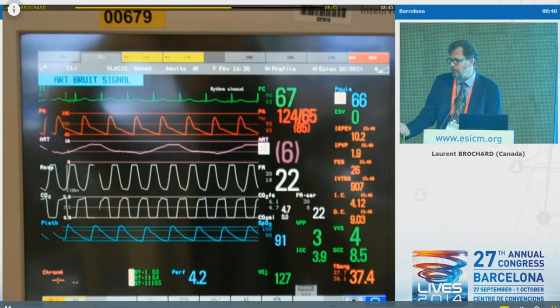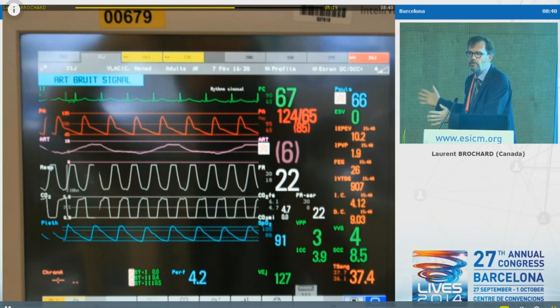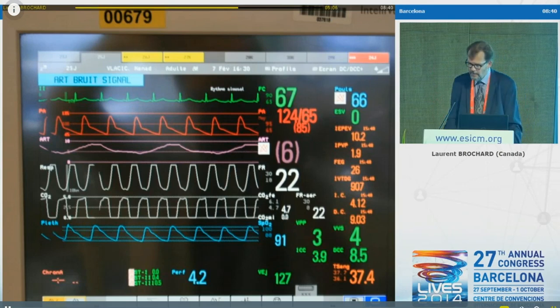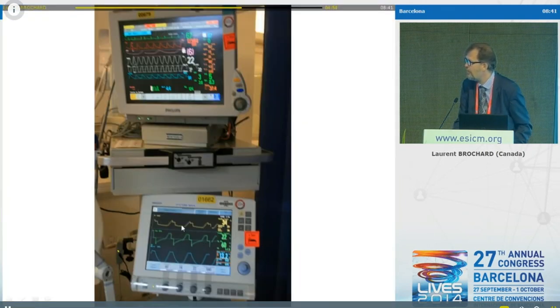Then you need a monitor. You need to display the signal. You may have your own monitor equipment, but the good news is that it's very easy to use the hemodynamic monitor at the bedside and to connect even the air-filled balloon catheter to the vascular transducer. And you see here, for instance, the tracing of esophageal pressure. You just have to remember that this is displayed in millimeters of mercury, whereas when you read the pressure on the ventilator, it is displayed in centimeters of water.